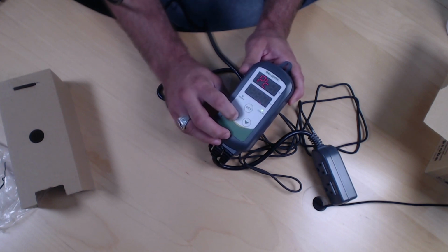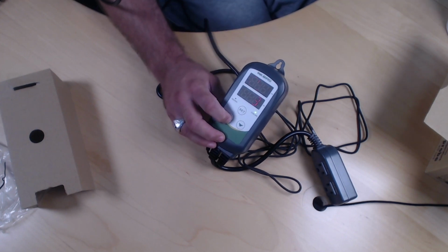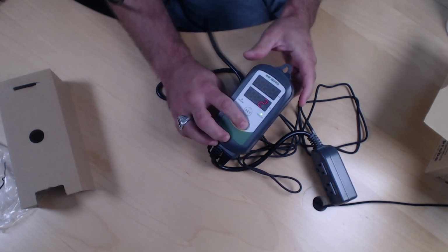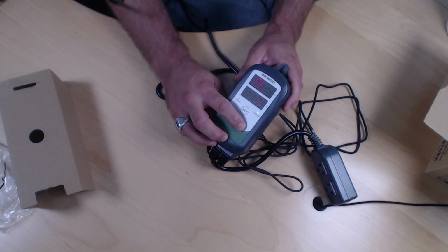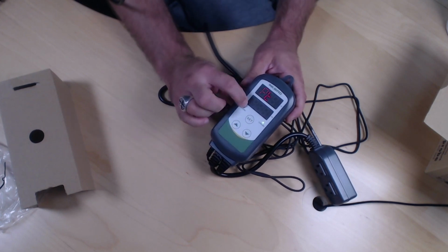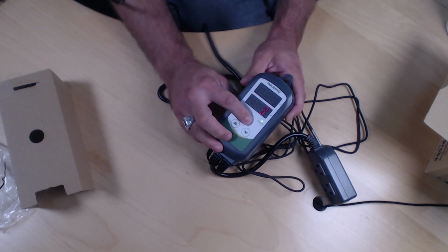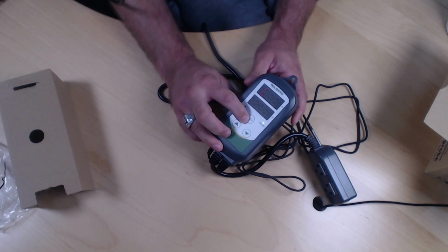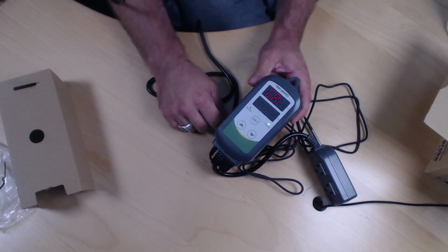Most people online that I looked up real quick, and I think the instructions actually might say it too somewhere, say that 3-minute or 4-minute is pretty standard and good. So we're going to set it at 3 there for the compressor delay and hit set to go to the next setting, which is probably the easiest one if you have a brand new unit.